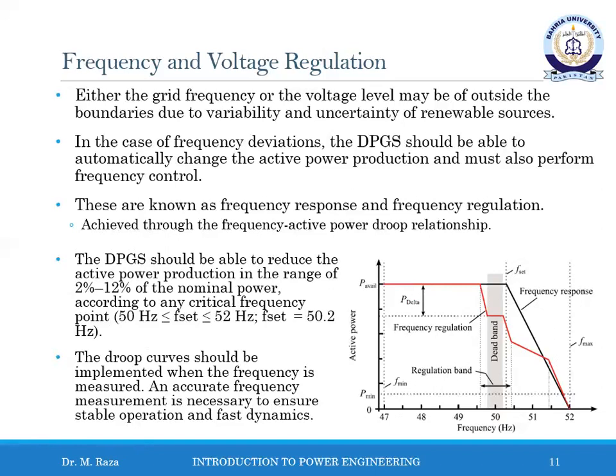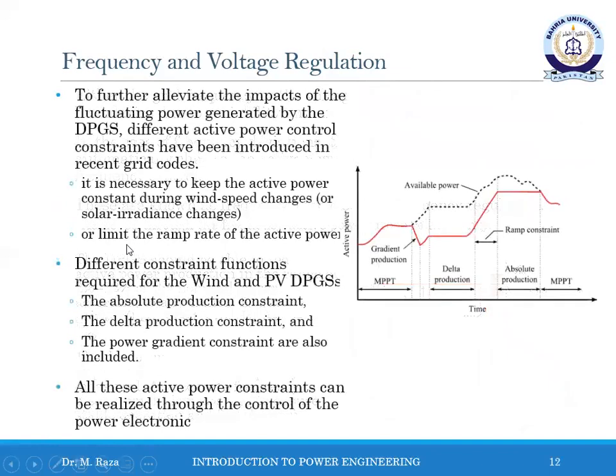The droop curve should be implemented when the frequency is measured. An accurate frequency measurement is necessary to ensure stable operation and fast dynamics. To further mitigate the impact of the fluctuating power generated by the distributed power generation system, different active power control constraints have been introduced in recent grid codes. It is necessary to keep the active power constant during wind speed changes or solar radiation changes, or limit the ramp rate of the active power.